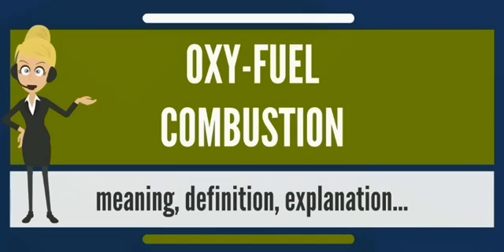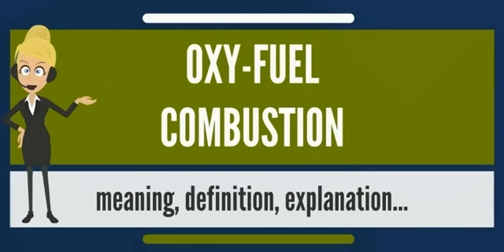Oxyfuel combustion has significant advantages over traditional air-fired plants. Among these are: the mass and volume of the flue gas are reduced by approximately 75%. Because the flue gas volume is reduced, less heat is lost in the flue gas. The size of the flue gas treatment equipment can be reduced by 75%. The flue gas is primarily CO2, suitable for sequestration.